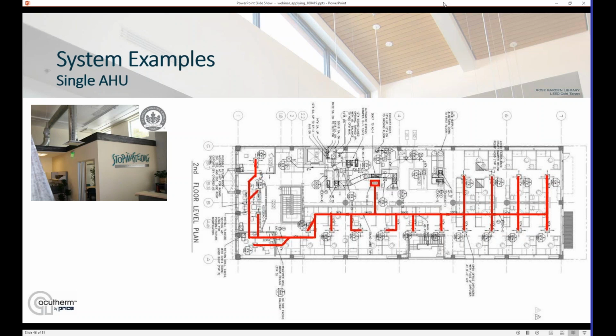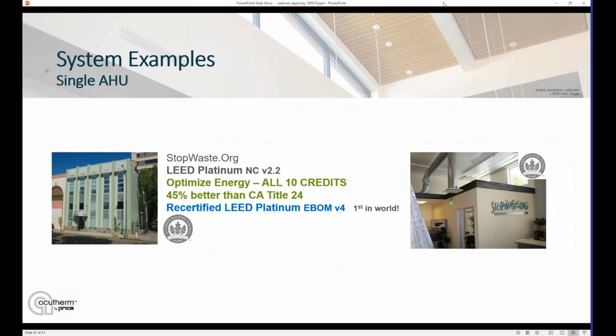It's an all low pressure system. So fan speed control, controlling the static pressure to the diffusers. And then without that, because it is a single zone, no need for reheat. The building will bring on some morning warm up when it needs it and either go into ventilation or cooling the rest of the time. That particular building, very energy efficient, as I mentioned.